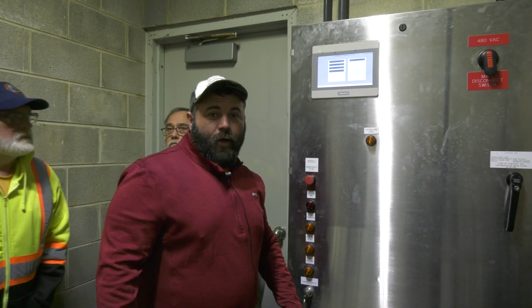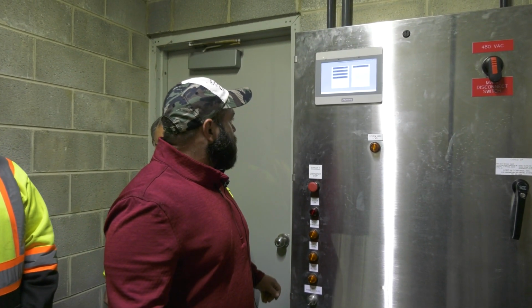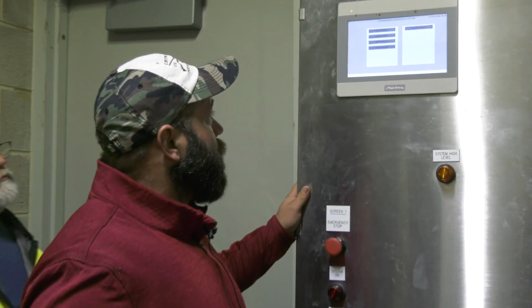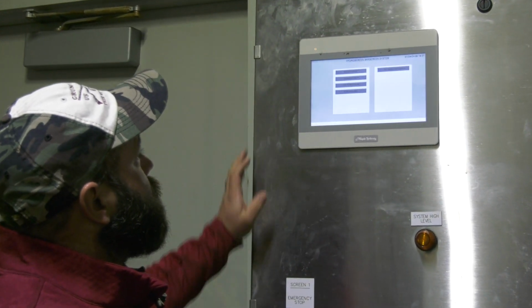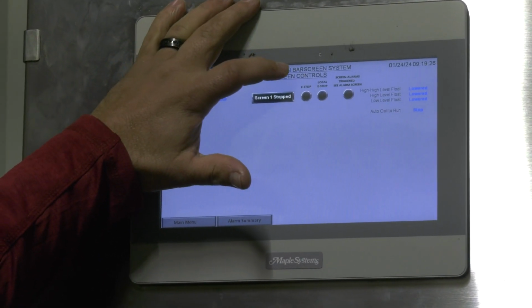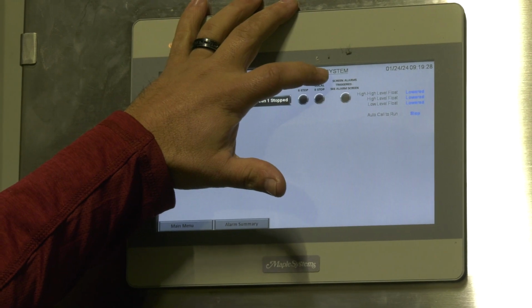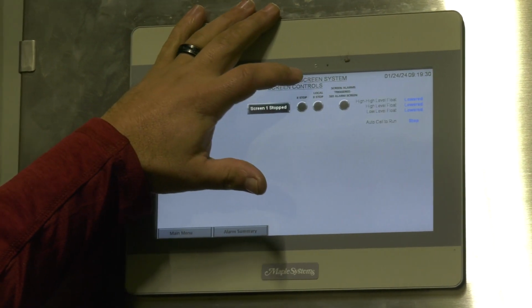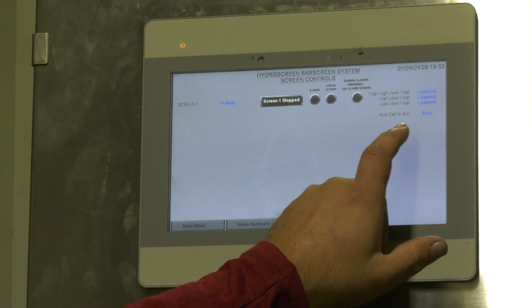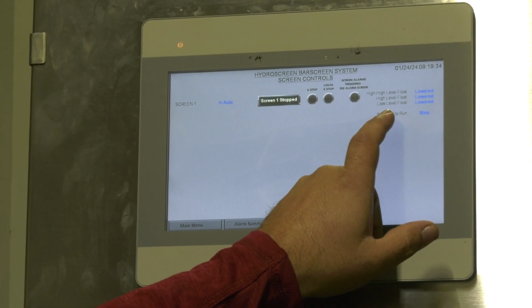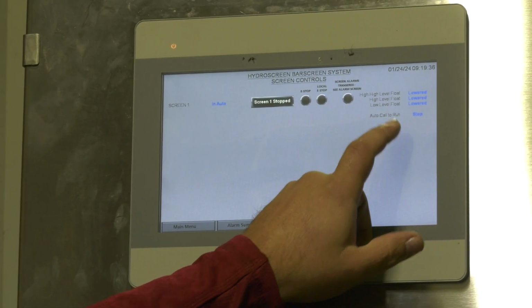Hey guys, Cagney Brown with the Bar Environmental. So today we're going to go over the control panel for the bar screens. We have the screen controls menu, which you go in here, gives you your e-stop, your local e-stop, your screen alarms, your triggered alarm screen. It tells you your auto call to run, is it stop, your low level float, high level float.